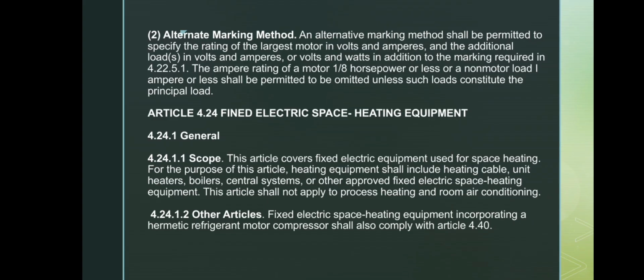Next, the slides introduce Article 4.24, Fixed Electrical Space Heating Equipment. General rules. These articles cover fixed electrical equipment used specifically for space heating. Examples include heating cables, unit heaters, boilers, central heating systems, and other fixed electric heaters approved for space heating. It does not apply to process heating, industrial heating, and room air conditioning. Additional requirements in Section 4.24.1.2: if the heating equipment includes a hermetic refrigerant motor compressor, it must also comply with Article 4.40, which covers refrigeration and air conditioning equipment.